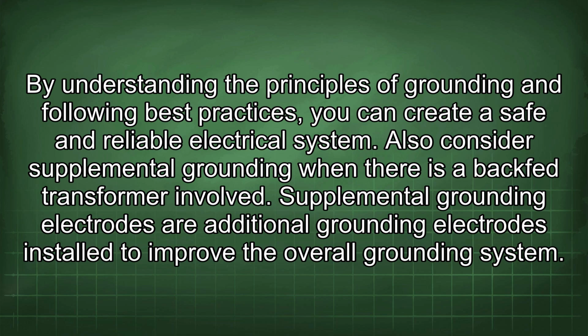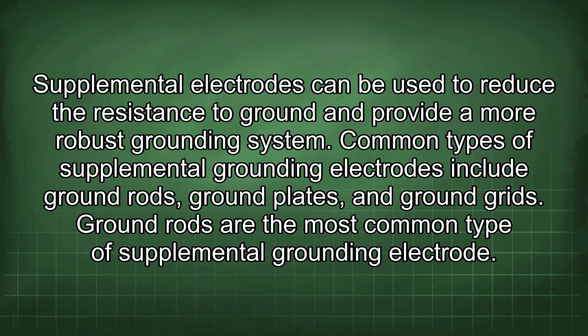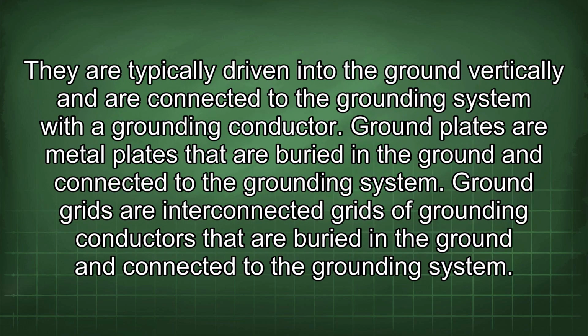Also consider supplemental grounding when there is a backfed transformer involved. Supplemental grounding electrodes are additional grounding electrodes installed to improve the overall grounding system. Supplemental electrodes can be used to reduce the resistance to ground and provide a more robust grounding system. Common types of supplemental grounding electrodes include ground rods, ground plates, and ground grids. Ground rods are the most common type of supplemental grounding electrode. They are typically driven into the ground vertically and are connected to the grounding system with a grounding conductor.